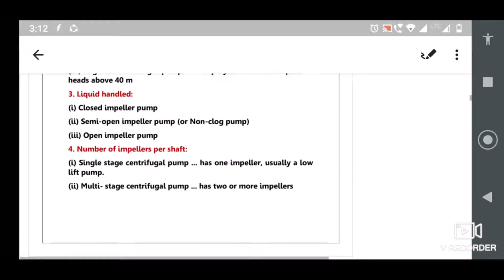Okay. And next, based on the number of impellers per shaft, you have the single stage one or the multi-stage one. Single stage usually has one impeller, for the low lift one, and where you go with multi-stage for the higher lift, you have 2 or 3 impellers in that. Okay. And again, next you have, based on the number of entries of your impellers, a single entry or maybe a multi entry. Based on that also you have a classification.